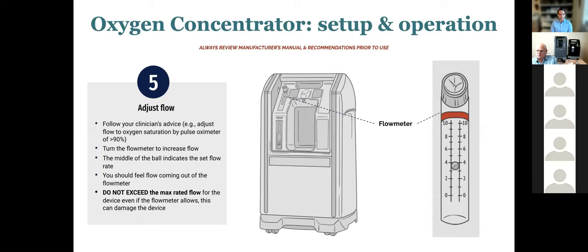In terms of flow, this is an important note. So the device, most devices will have a flow meter on the top front of the panel. You can see it here blown up. This particular flow meter goes from 0 to 10 liters a minute. The range of flow is going to be different depending on what your device can put out. Some devices may only put out 5 liters per minute, some even less, and some devices may not go all the way down to 0 liters per minute on the flow meter. They may have a minimum flow of closer to 2 liters per minute. The relevance of that is if you're using the concentrator to take care of infants or neonates or patients that you want to have less flow, then you would need another flow meter downstream.